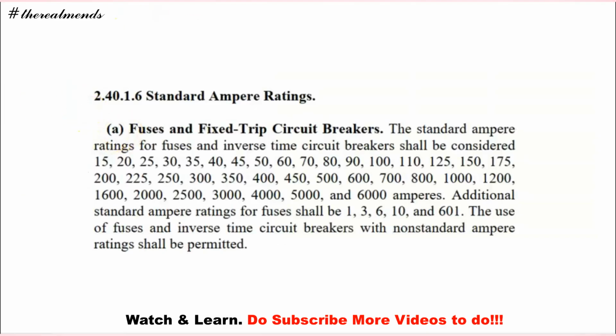Okay, so from table 2.40.1.6, standard ampere rating, so fuses or fixed-trip circuit breakers. The standard ampere rating for fuses or inverse time circuit breaker shall be considered 15 minimum. Next is 20, 25, we have 30, 35, 40, 45, 50, 60, 70, and so on.